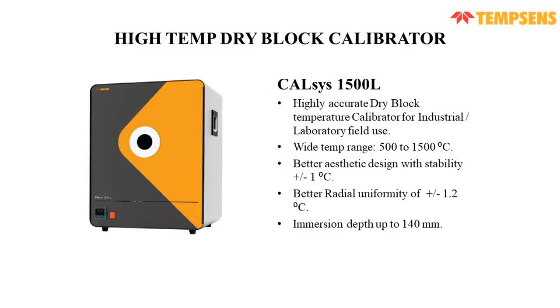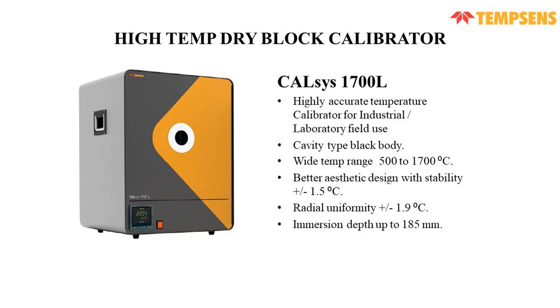Next, we have CALsys 1500L, which is also a very highly accurate dry block calibrator with a wide temperature range of 500 to 1500. The stability is plus minus 1 degree and the radial uniformity is plus minus 1.2 degree, and it has an immersion depth of 140 mm. Next, we have CALsys 1700L. It has 500 to 1700 degrees centigrade for the temperature range, and for the stability it has plus minus 1.5 degrees centigrade with radial uniformity of plus minus 1.9, and it has an immersion depth of 185 mm.